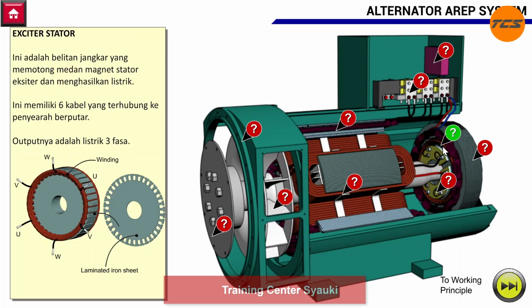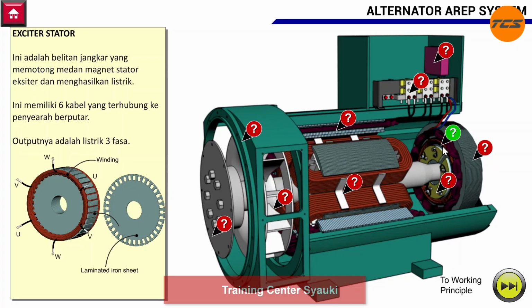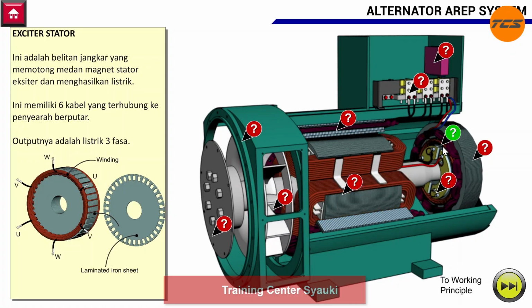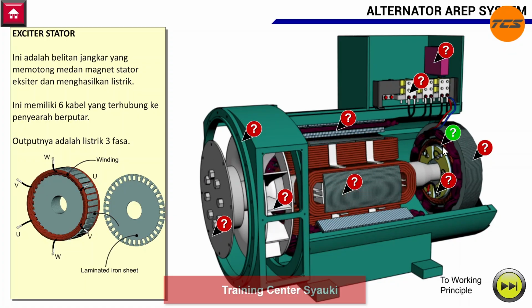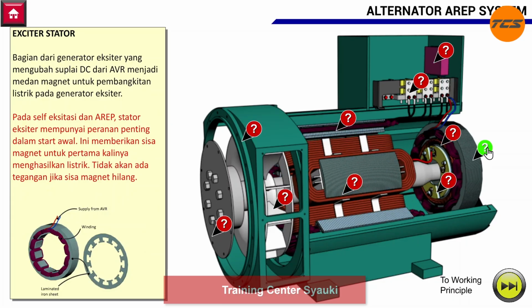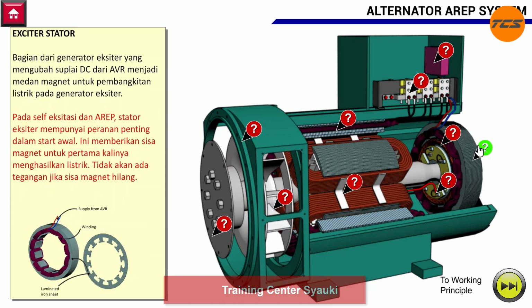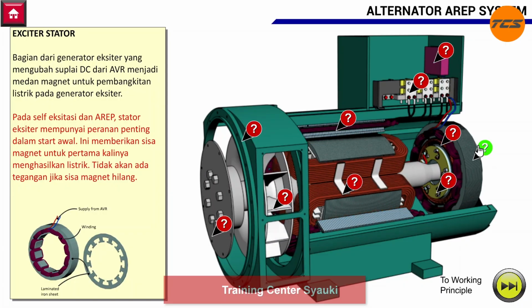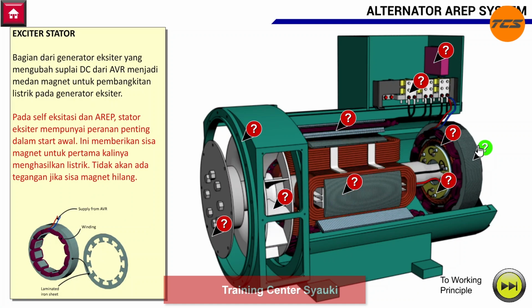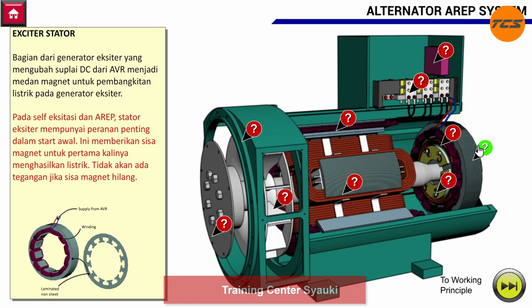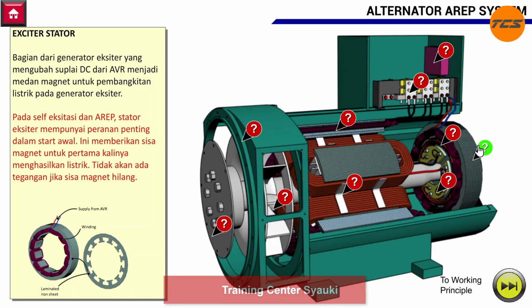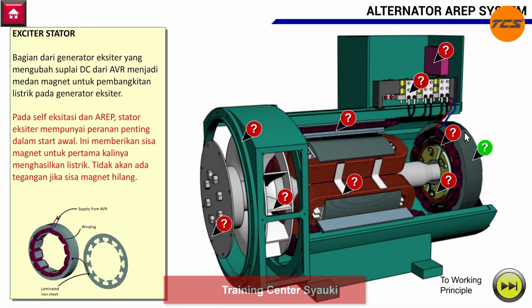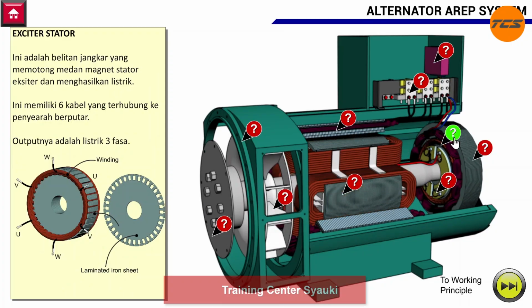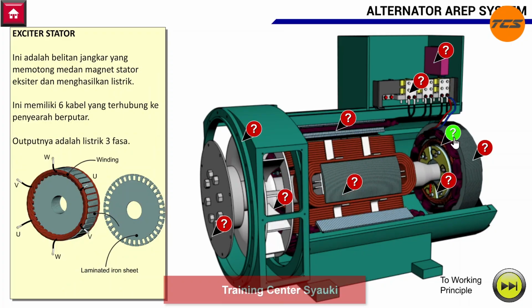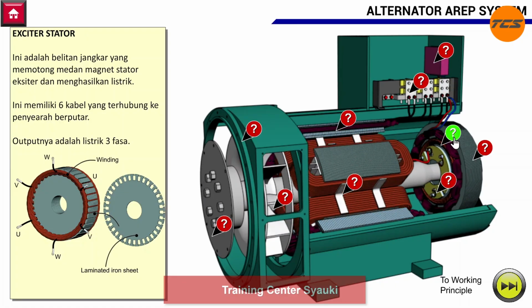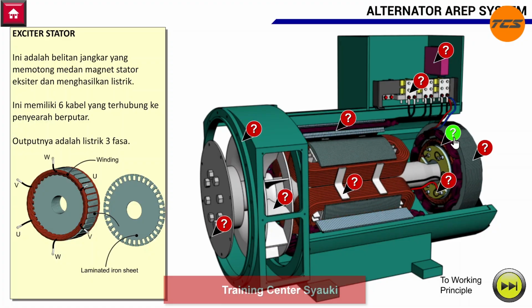In the exciter system, the exciter rotor contains the armature winding. The exciter stator contains the field winding. The exciter stator receives DC power from the AVR, or automatic voltage regulator. This DC current creates a magnetic field in the exciter stator. When the exciter rotor rotates within this magnetic field, it generates three-phase AC voltage in the exciter rotor winding. This AC voltage is then rectified by the rotating rectifier and supplied as DC to the main rotor.